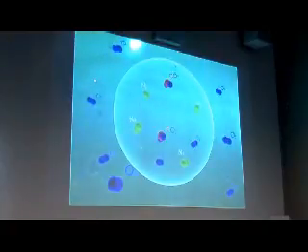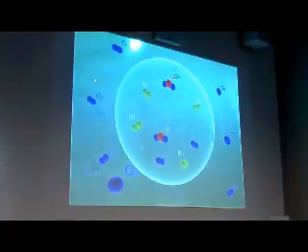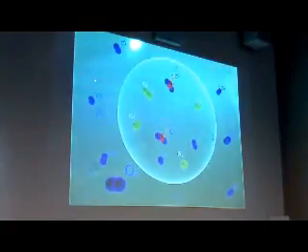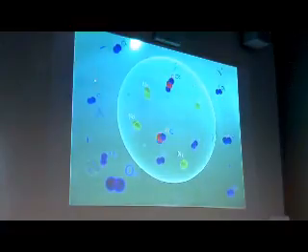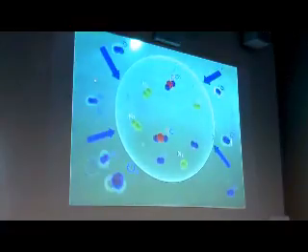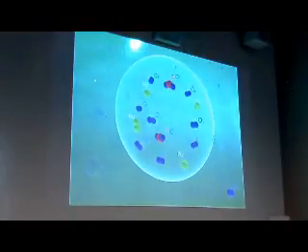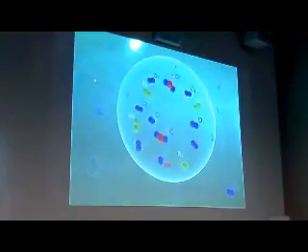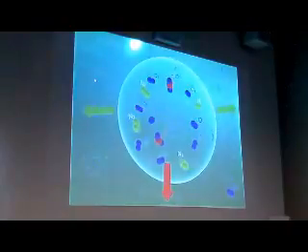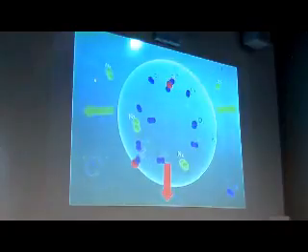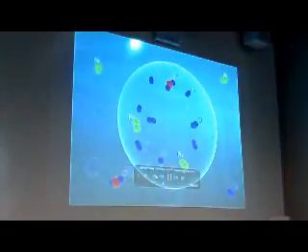Now, as low oxygen gas bubbles pass through the water piping, dissolved oxygen in the water diffuses from the water phase into the gas phase as a new equilibrium is established with 95% lower dissolved oxygen in the water. The gas strips oxygen out of the water. At the same time, a small amount of carbon dioxide and nitrogen gas pass from the gas phase into the liquid phase.